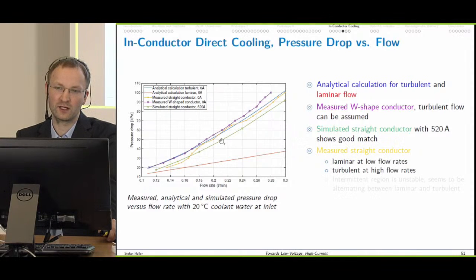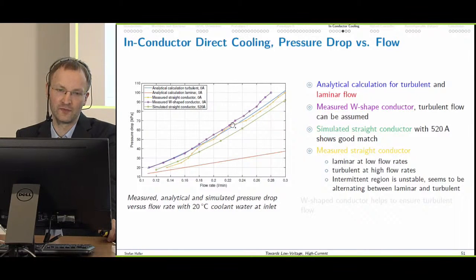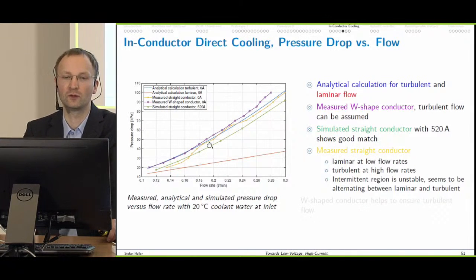However, for the yellow conductor, which is the measured straight conductor, it's a bit different. We can assume laminar flow at low flow rates, and we can assume turbulent flow at high flow rates. And in between, this is unstable. So we can assume that we have dynamic changeovers from laminar to turbulent. And that was confirmed by the temperature sensors we have on the conductor.